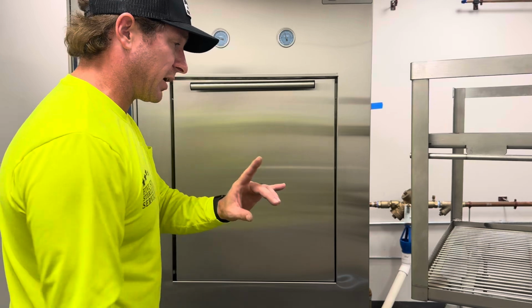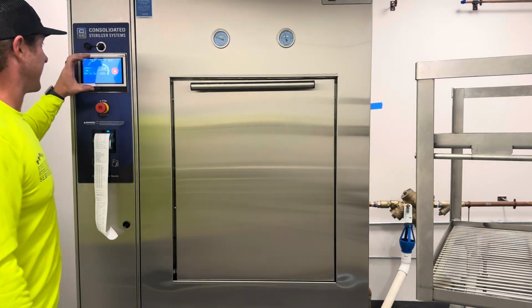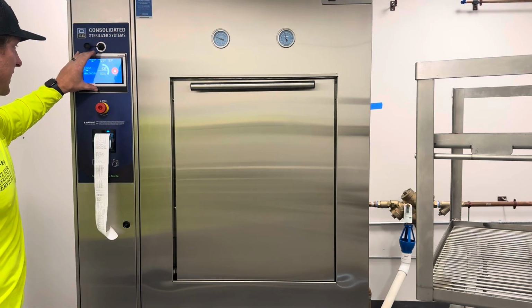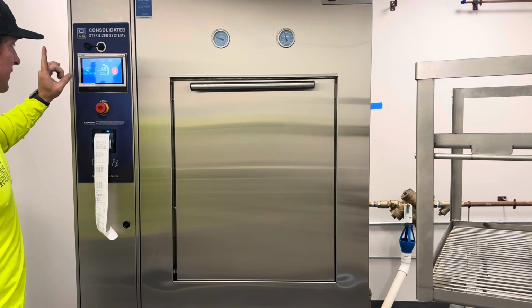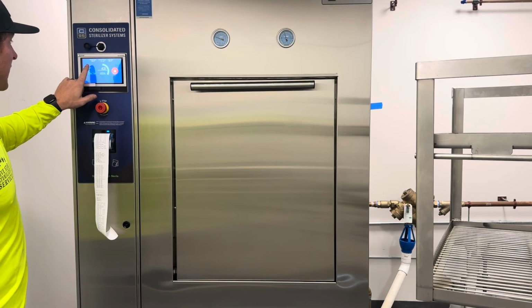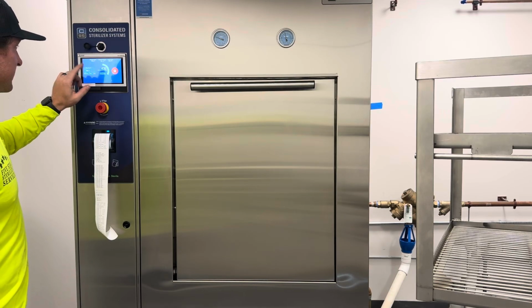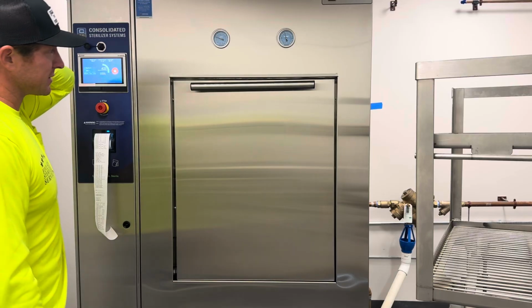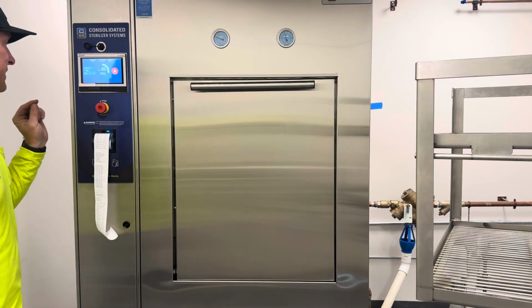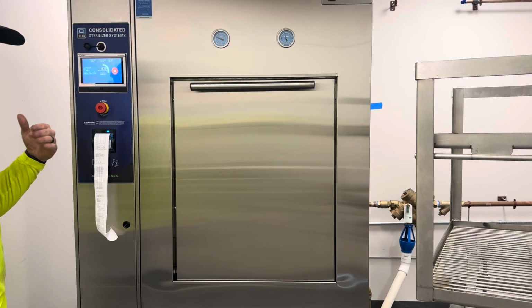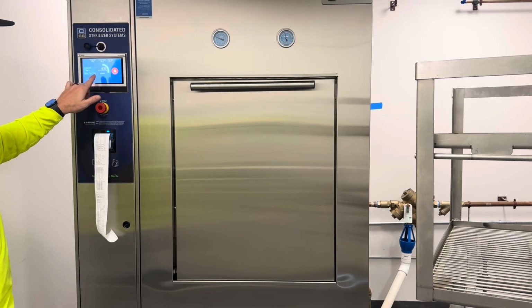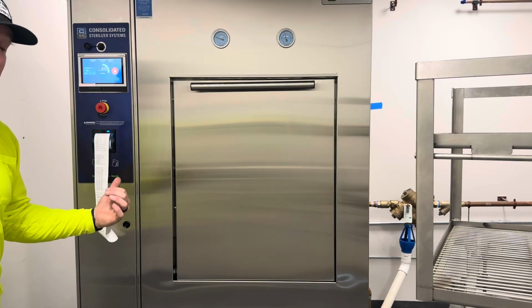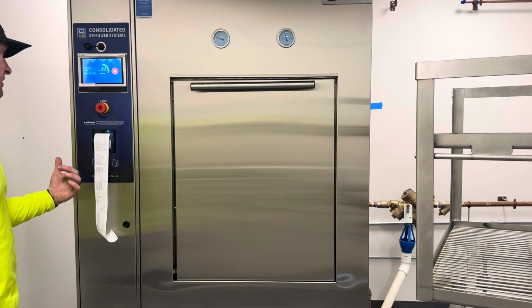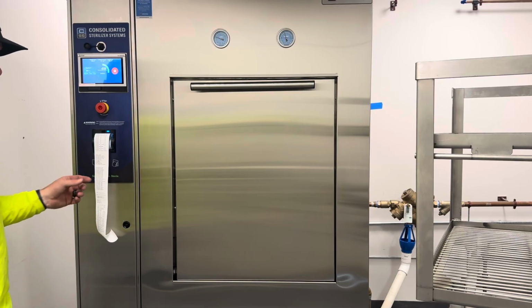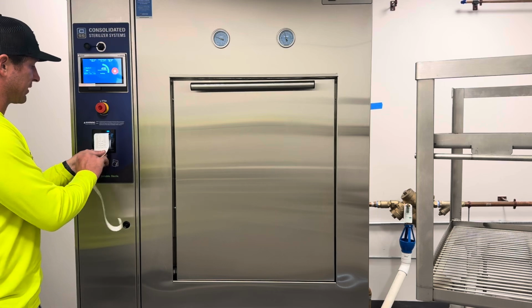Okay, we're going to pause on the carton carriage for a second and go back. We're in the stabilize phase of this cycle right now. That goes on for 1 minute because we've satisfied our temperature at 122 degrees. Our pressure's at 17, 18 psi, which correlates. As soon as that 1 minute stabilization countdown completes, it will go into the sterilizing phase, which it just did. So we've got 1 minute of sterilizing, and then it's going to go into the exhaust phase. And I guess we'll just let this cycle go ahead and complete all the way.